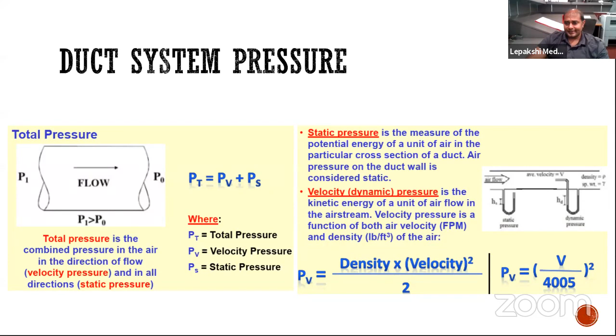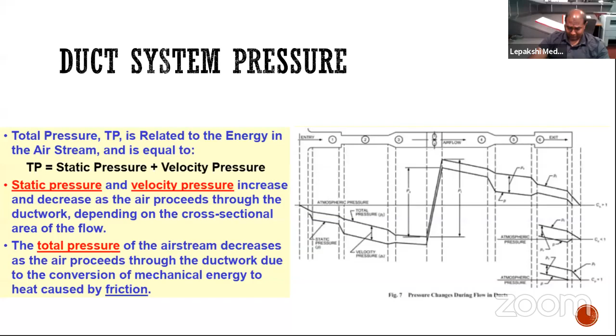Like for instance, on this diagram over here, this is the ductwork. The top line represents the total pressure of the system, where over here you're putting in a fan, which means you're manually adding pressure. That's why the pressure rises over here. Otherwise, it's going to go down like this. The total pressure is always going to go down with friction losses and so on, whereas the static and velocity pressures will change. They can go up or down depending on the orientation, the cross section of the duct, the equipment, and so on. The total pressure always goes down unless you put fans in the ductwork, but the static and velocity pressures can go up and down. It depends on the system, like the shape of the fitting.